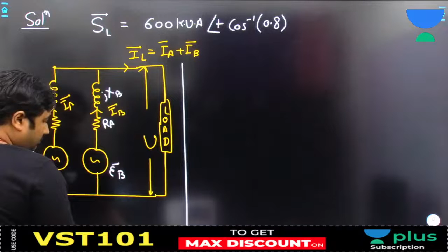Now please see, the kVA shared by transformer A, conjugate, will become, sir, SL conjugate into ZB upon ZA plus ZB. Now it is very important to select a common base for both, because if you divide each impedance by Z base, then Z base will cancel out only if the per unit impedances are on the common base. Is it okay? Yes, sir. So you can say, sir, in this formula, ZA and ZB are either in actual ohms or in per unit on common base. So I am writing here, where ZA and ZB are in per unit on common base or in actual ohms.